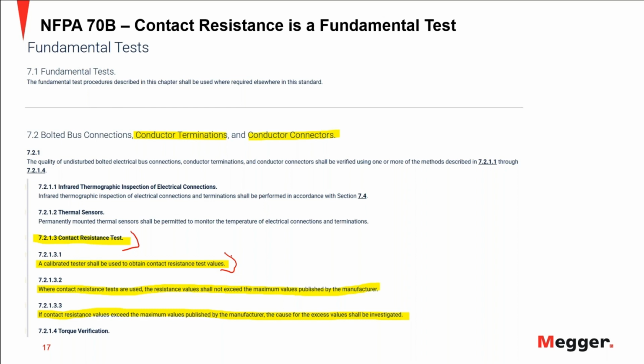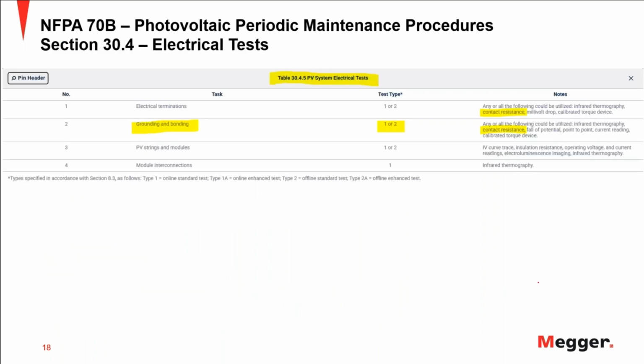And once you have those results, you want to compare them to the values published by the manufacturer or the manufacturer's specifications, and anything deviating from that shall be investigated. So it's mandatory. It's an actual fundamental test, and they want you to get actual values. NFPA 70B has a section, 30.4, for electrical tests, which is for testing photovoltaic systems. And again, it shows that you should test your grounding and your bonding. They talk about several methods, and one of the methods is contact resistance. However, let's talk about the other methods: infrared thermography, fall of potential, point-to-point, current reading, and calibrated torque.